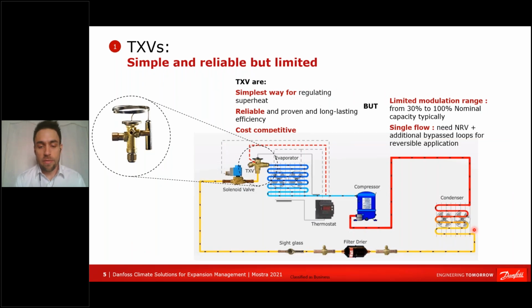Let's start with a very simple schematic of the TXV, the way most devices usually do expansion. Here you have a very simple condensing unit schematic using a TXV. The TXV can regulate superheat, meaning you have a probe connected to the end of the evaporator, and then mechanically it can open or close the valve so the superheat is regulated to a certain value set once and for all in the factory. This is very reliable, simple, cost competitive, has worked for decades, and will still work for many applications, but it has some limitations.